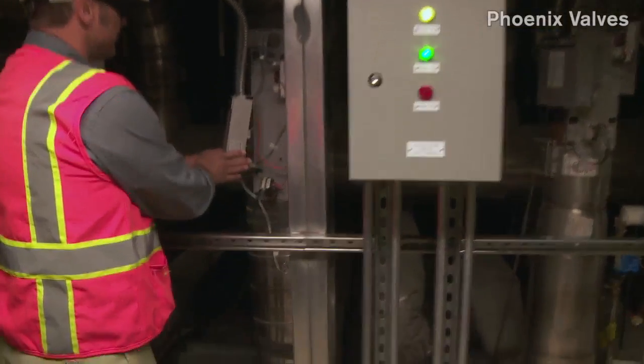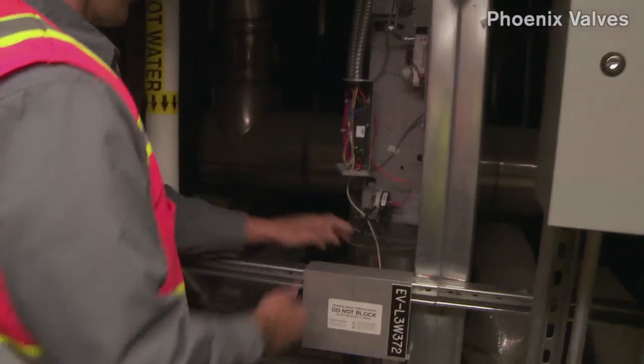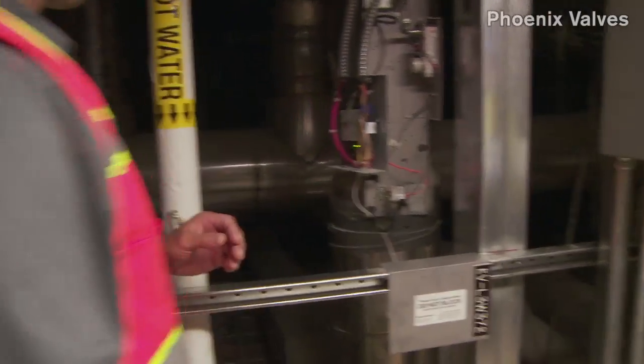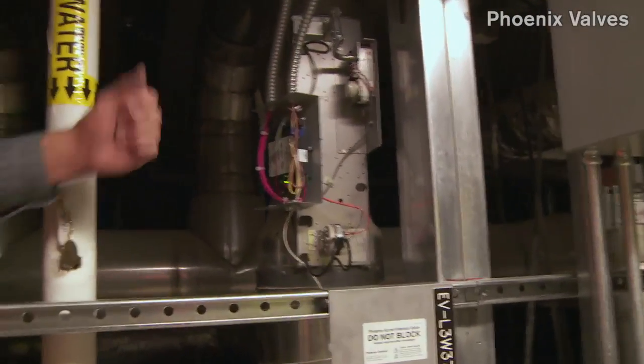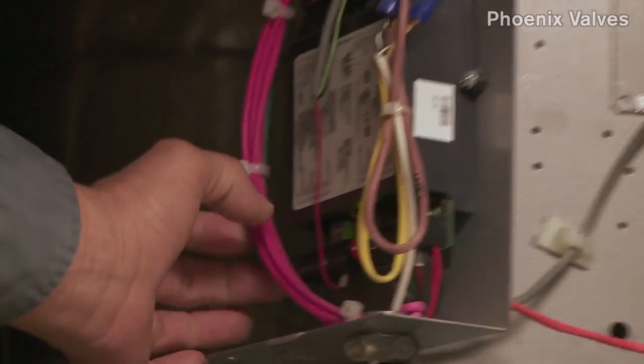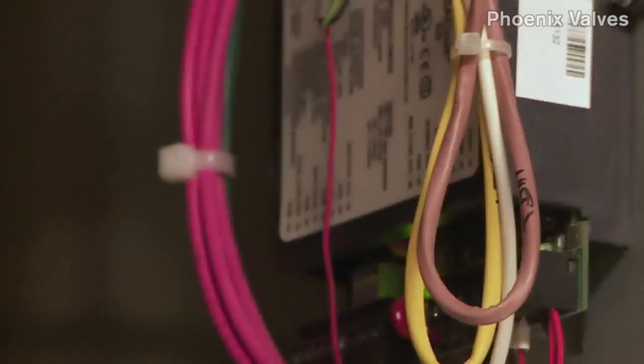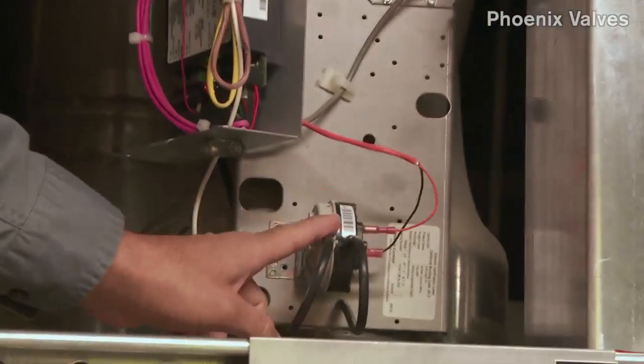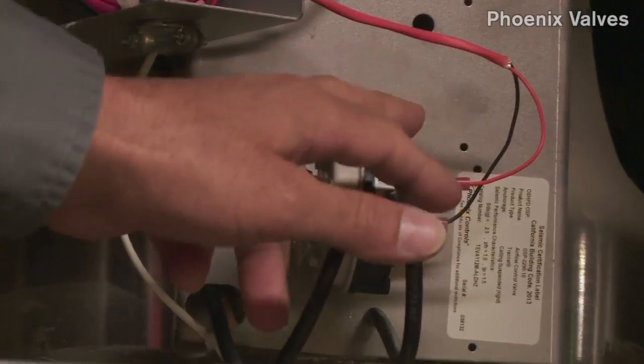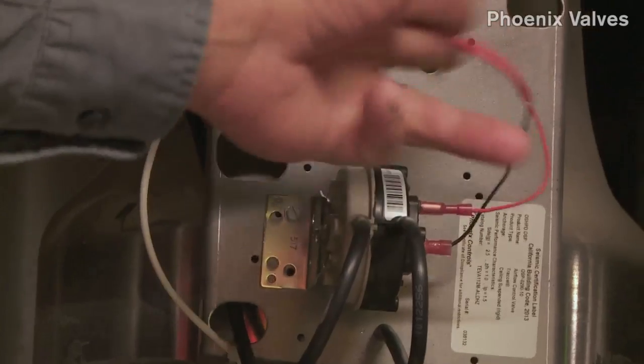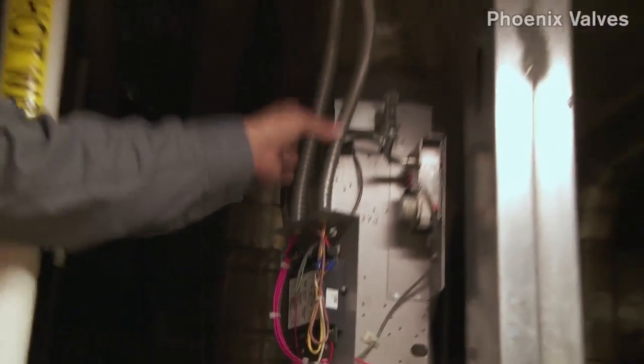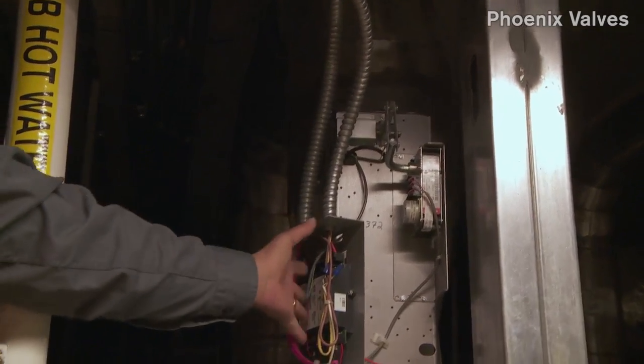So I'm going to go ahead and take off the controller cover here. So we have a BACnet controller board. It's supplied with 24 volts AC. The pressure switch is a dry contact with the air coming through here. When it gets closed, these two connectors are run through an orange wire. Actually, on this system, like I said earlier, it's running straight to Johnson Controls. It doesn't even land on our board.